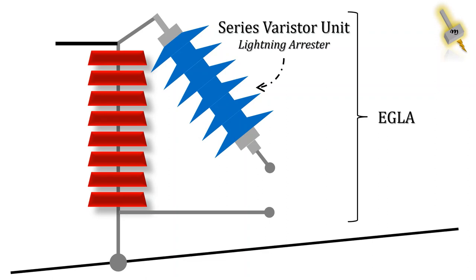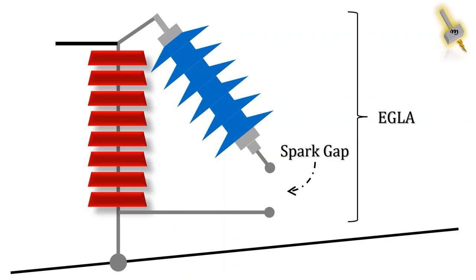The SVU is rated for nominal line to ground voltage, which means after the surge event, when the normal system voltage is restored, the SVU should interrupt the follow on current. Then we have the spark gap, which is rated as per critical flashover voltage of insulator, which means before the insulator flashes over, the spark gap should flashover.